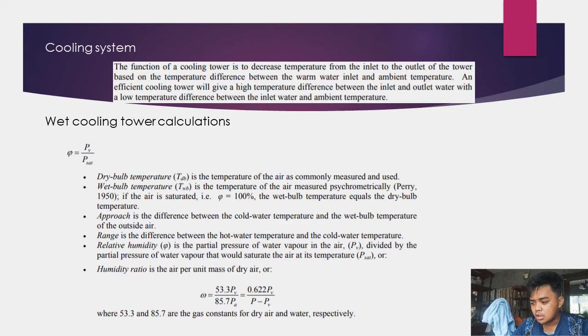Relative humidity is the partial pressure of water vapor in the air divided by the partial pressure of the water vapor that would saturate the air at its temperature. Or humidity ratio is the water vapor per unit mass of dry air. Or omega is equal to 53.3 P sub V over 85.7 P sub A, which is equal to 0.622 P V all over P minus P sub V, where 53.3 and 85.7 are the gas constants for dry air and water respectively.